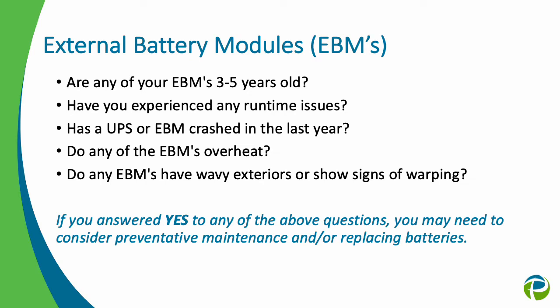We recently pulled some EBMs out of a customer's closet that had been there a little too long. When we opened up the UPS and EBMs, the batteries inside were actually wavy and bubbled. That showed us those batteries were overheating. If those batteries were left to their own devices for another few years, they could have caught fire, or even in just the right scenario, a perfect storm, caught fire.